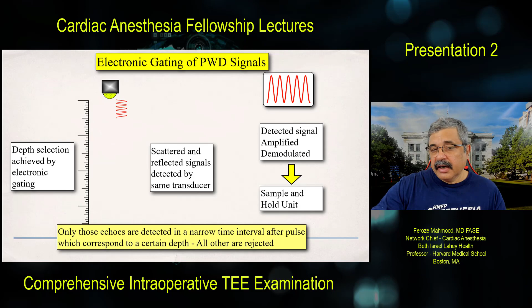So this is the reference signal, like we send it out in continuous wave Doppler. However, the received signal is only coming after certain times. While reflections start to come back immediately, as soon as transmission starts, we are interested only in the ones that are coming from the sample volume. And how we know which ones to analyze are the ones which take a certain specific time based on the depth. So these are the reflected signals, and we are receiving time-gated pulses from the sample volume.